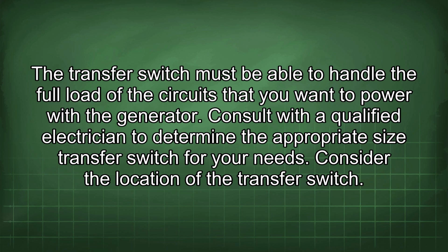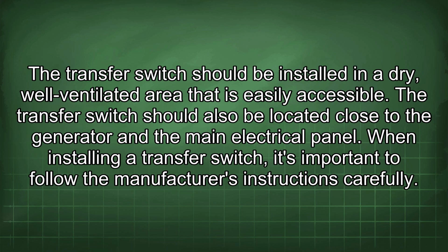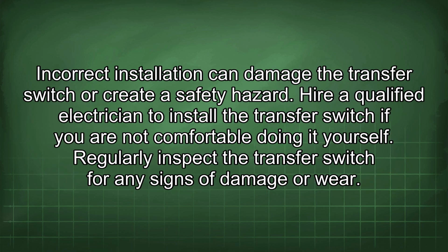Consider the location of the transfer switch. The transfer switch should be installed in a dry, well-ventilated area that is easily accessible. The transfer switch should also be located close to the generator and the main electrical panel. When installing a transfer switch, it's important to follow the manufacturer's instructions carefully. Incorrect installation can damage the transfer switch or create a safety hazard. Hire a qualified electrician to install the transfer switch if you are not comfortable doing it yourself.